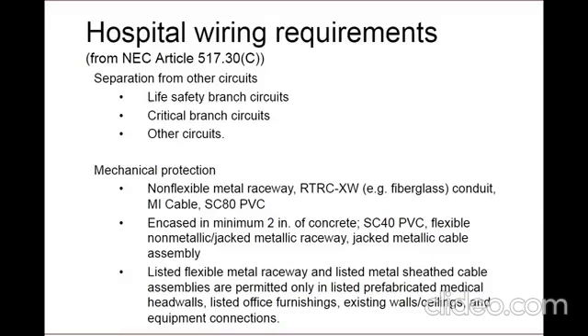NEC 517.30(C)(1) requires the wiring for the life safety branch and critical branch to be kept entirely independent of all other wiring and equipment, including from each other. That means separate raceway systems, including conduit supports, boxes, etc. Mechanical protection from damage of essential electrical system, life safety, and critical branch wiring is addressed in NEC 517.30(C)(3).